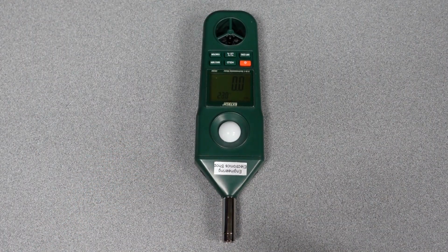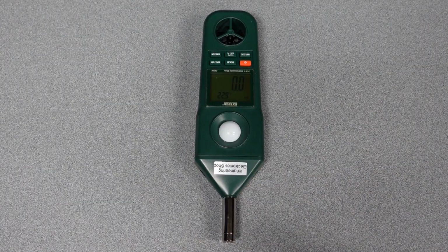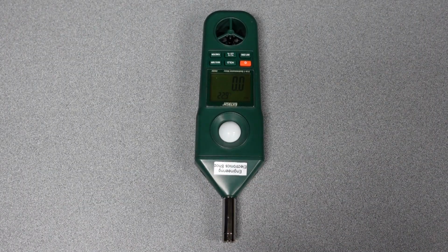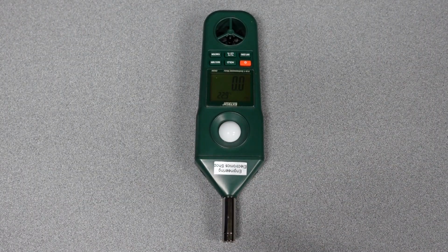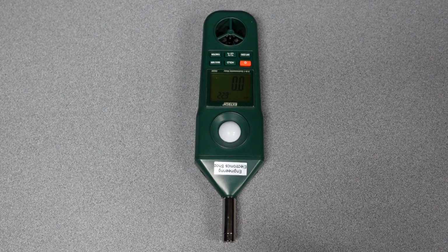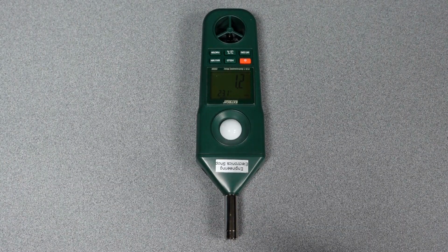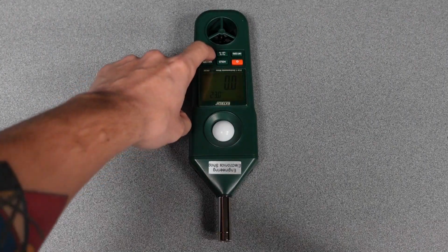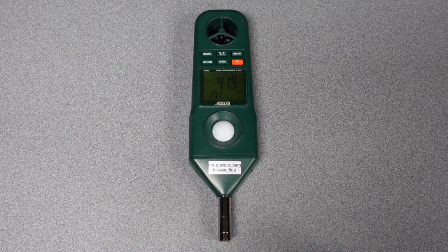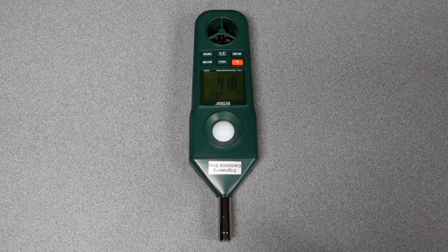Note that with any function where temperature and another measurement are shown, the meter only records the other measurement. In this case, it recorded only the wind speed. Furthermore, one can also press the hold button to stop the display from updating and only display the most recent measurement. The next function measures relative humidity and temperature with the internal sensor. Relative humidity is recorded up to 80%.